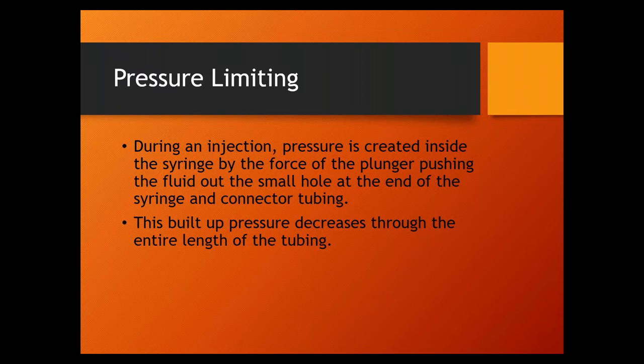The pressure limit is not a goal - it's just saying don't exceed that number, and that pressure is not in the patient. Sometimes operators don't understand this and will call the biomed department saying their injector is pressure-limiting during the shot. The first thing to ask is what their pressure limit is set to - they'll say something like 50 PSI, not wanting to put 300 PSI in the patient. But for CT and MRI injectors, 300 PSI is the correct default. Angio injectors, with their much higher 40-50 mL/sec flow rates, can go up to 1,000 or 1,200 PSI in the syringe.